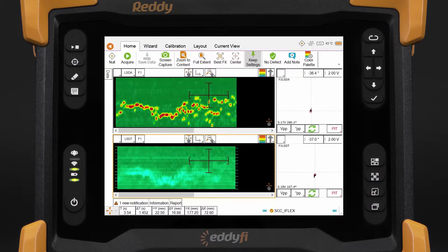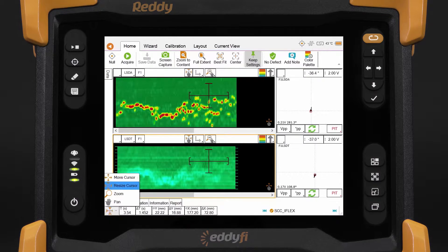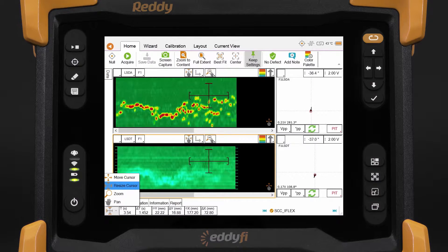If you want to change the operating mode of the arrow, press the upper button, which will cycle through the different modes available for the C-scan. Pressing it shows the different possibilities: move cursor, resize, zoom, and pan.